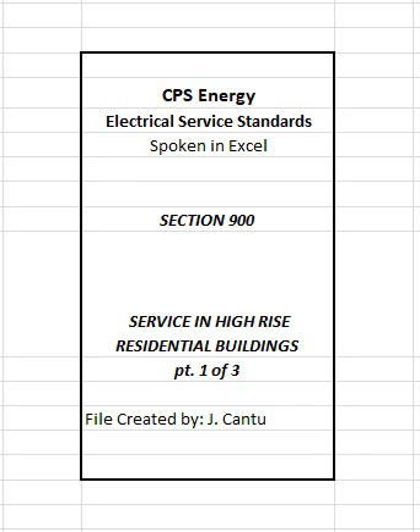925 Meter room disconnecting means, device. Customer shall furnish, install, and maintain a readily accessible fuse disconnect switch or circuit breaker in meter room ahead of group metering equipment. Disconnecting means shall be installed within 6 feet of point of penetration by customers' feeder conductors into meter rooms. A modular metering unit's main disconnecting means shall be acceptable for this purpose. 926 Metering equipment. Customers' design drawings shall include proposed metering equipment on the load side of meter room disconnecting means that will be used to supply tenant loads, refer to Article 904.